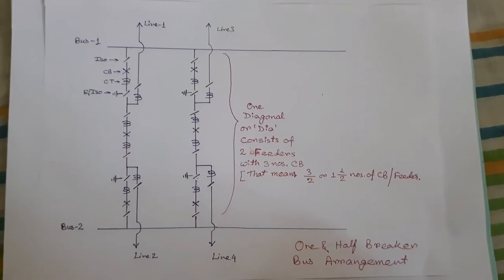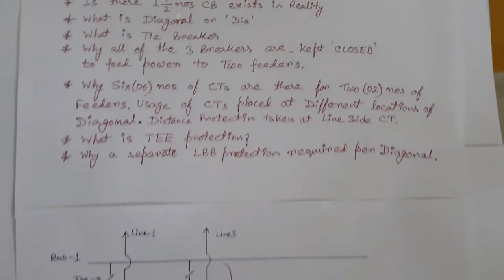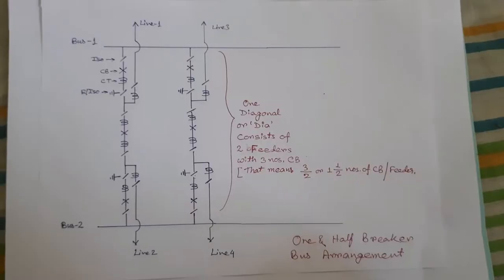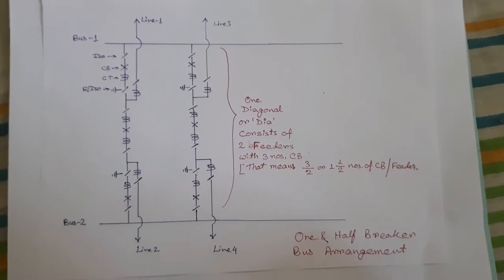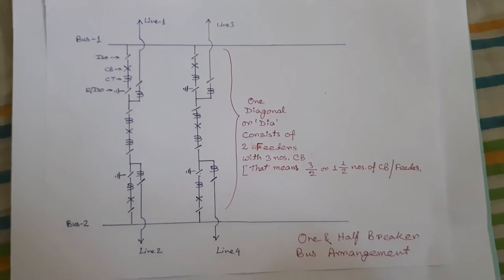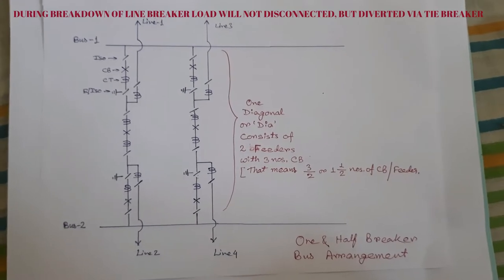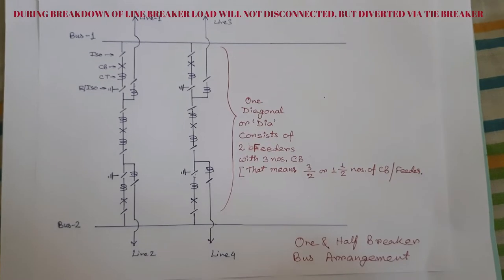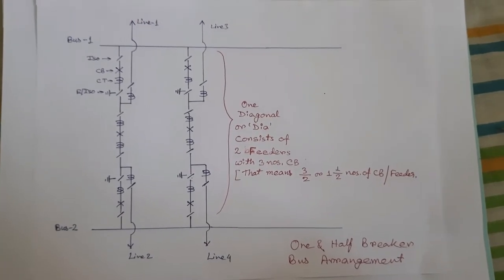In this video, we will do some point-wise discussion on the one and half breaker scheme. One and half breaker scheme is actually one kind of bus arrangement, like the one main one transfer scheme or two main bus one transfer bus scheme. In the one and half breaker scheme, there are three circuit breakers used for two feeders.